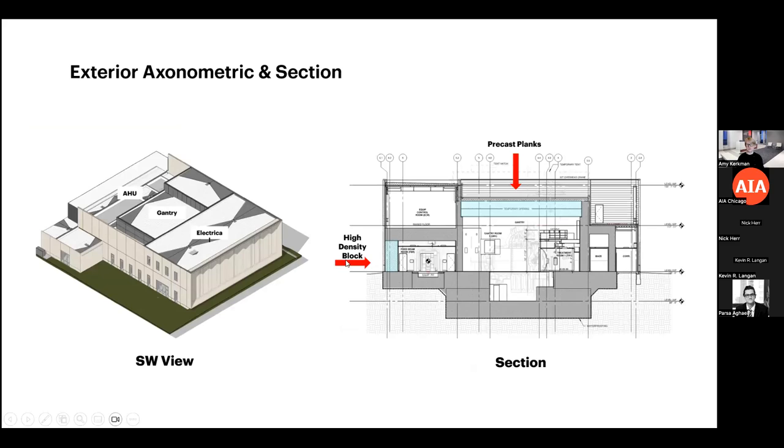A section through both treatment rooms shows the large gantry room with a deep pit. There is a roof opening through which a crane will bring the large gantry into the vault, with a built-in vault crane for precise placement, and the roof will be infilled with precast planks. The smaller vault for the Leo Cancer Care upright equipment has the nozzle entering through a side opening, which will be infilled with high-density block. The slide also shows the electrical area at the top, the gantry in the middle, and two air handlers supporting the proton therapy.